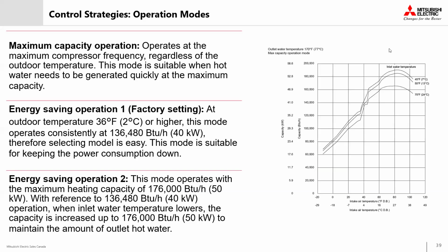Just quickly looking at different operating modes for this particular QHV system that we've referenced here today. Most manufacturers do offer several different operating modes in their CO2 heat pump water heaters, giving operators flexibility to adapt to changing building needs and conditions. Here we'll walk through a few examples of one of our own heat pump water heating units. Like I mentioned, QHV is our reference point here today.